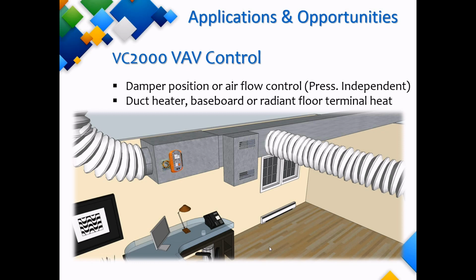The VC2000 is available in 2 models, pressure dependent and pressure independent. The pressure dependent model does not have an airflow sensor, while the pressure independent model has an airflow sensor for accurate airflow control. The VC2000 controller also has 1 digital output and 1 analog output, which can be used for any reheat, whether it's electric or hot water, modulating or staged. The outputs can also be set up for fan-powered boxes, baseboards, or zone valves. You can also connect a slab temperature sensor and control the slab temperature for radiant floor applications.